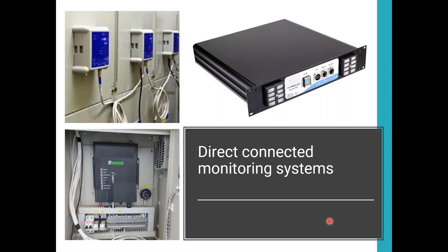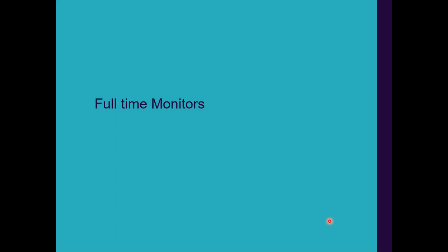Now, the next level up is full-time monitoring. The online tests, the instruments that I just talked about, level one and level two, are all online. They use system voltage and frequency for their voltage levels. One thing it's not telling you, that the offline test does, is the inception and extinguished voltage. But if you go in there and you have PD at your nominal voltage level, the extinguish and inception voltage don't count that much anymore because it's there now. You know it's present during your normal operating system, so it's more of a concern. It's already in your operating range.